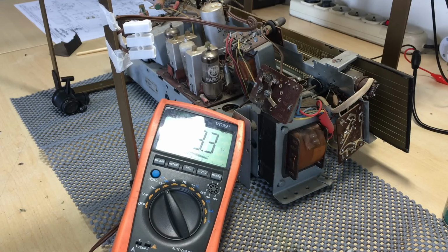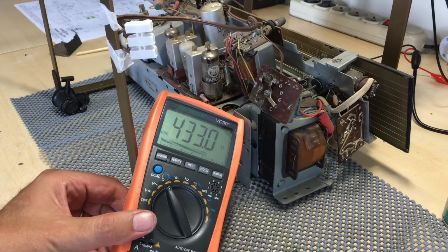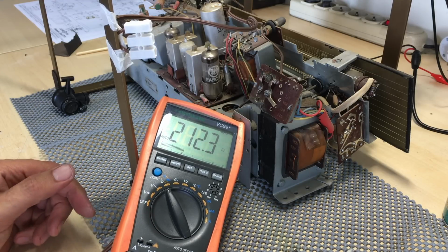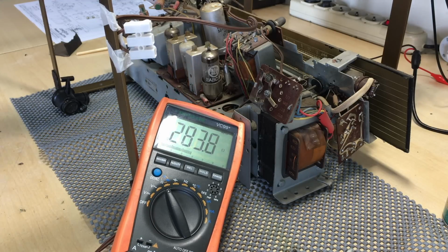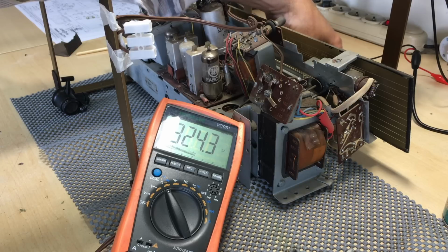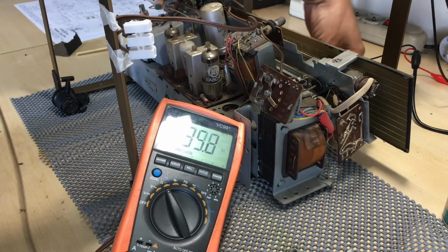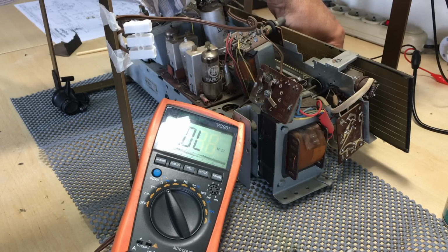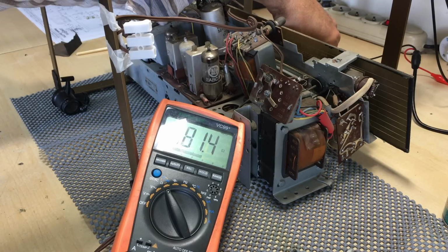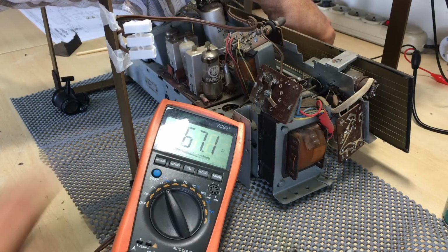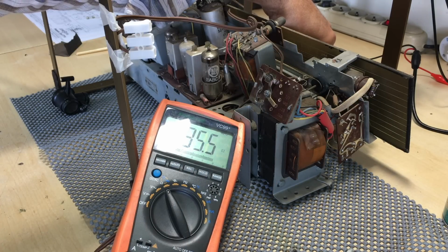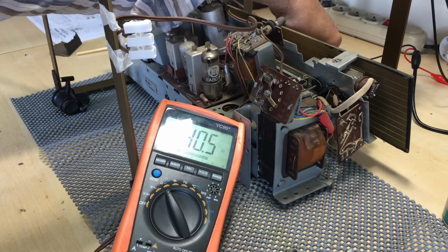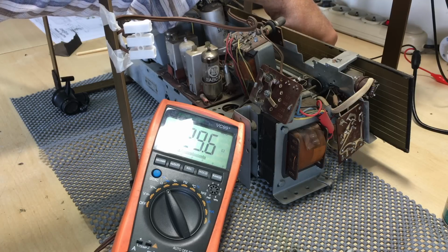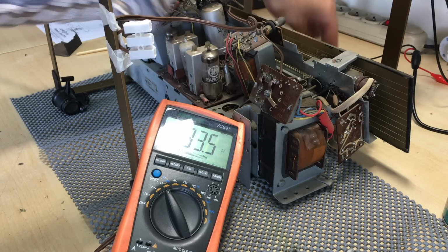We're getting 400 ohms, jumping around in the low ohm range. If I hit this side... open, closed. That's still got to do with a bit of corrosion on that contact, but we've got 400-something ohms. We should be reading about 40 ohms, which is what we get before the fuse. So I'll clean the switch contacts as well and see if we can improve that.